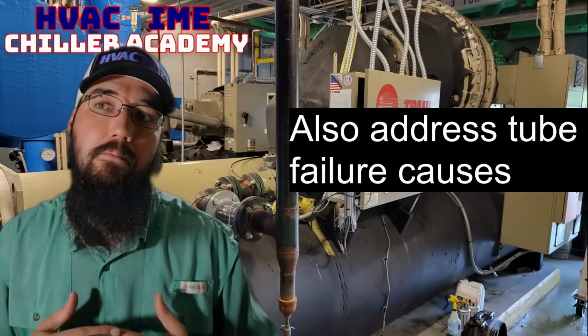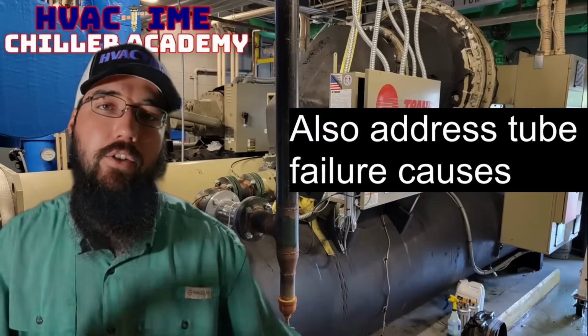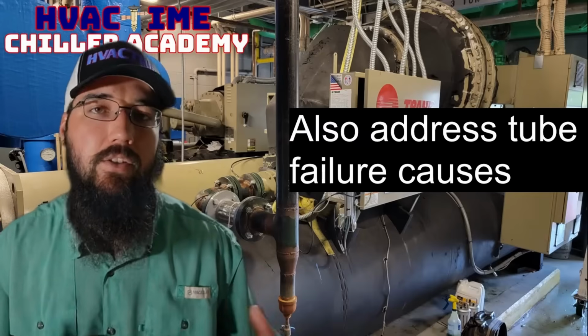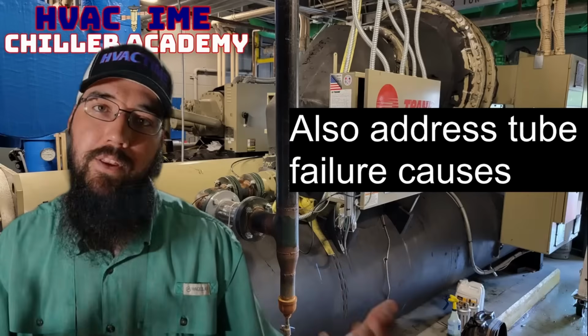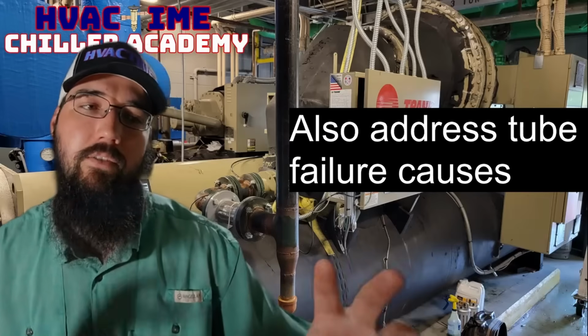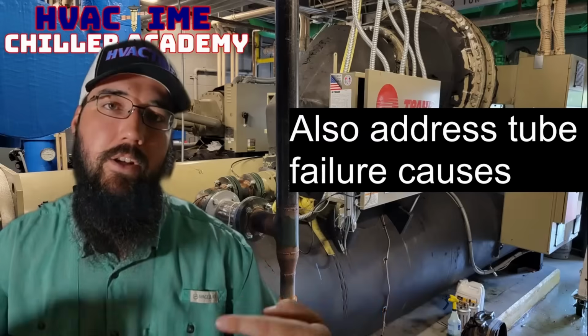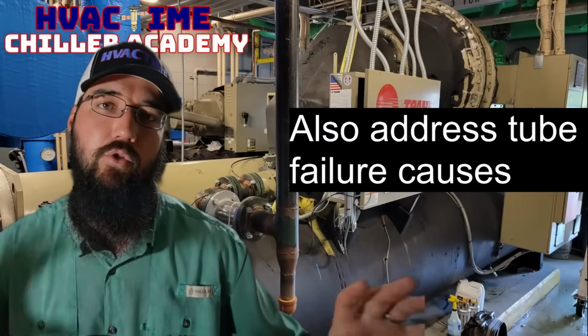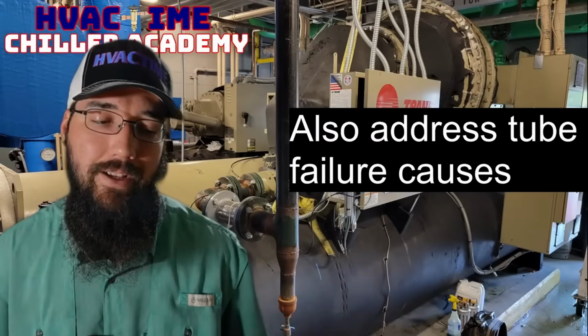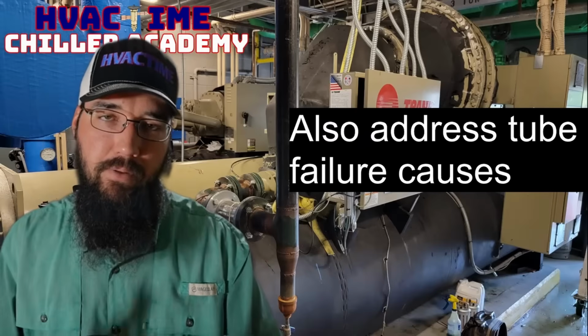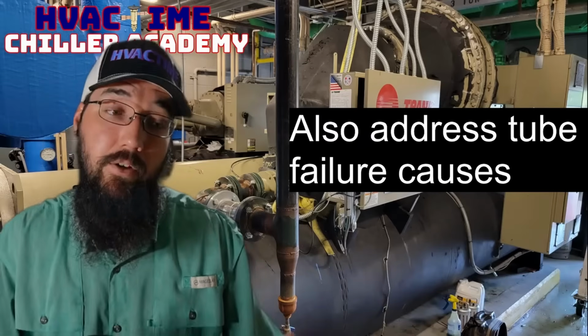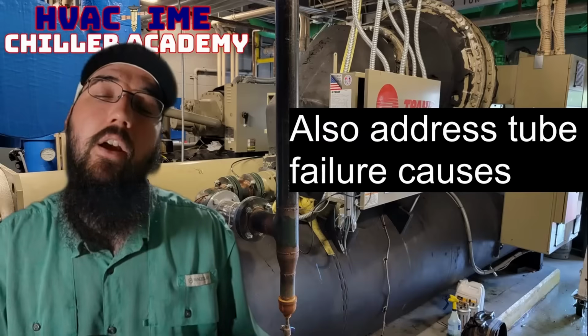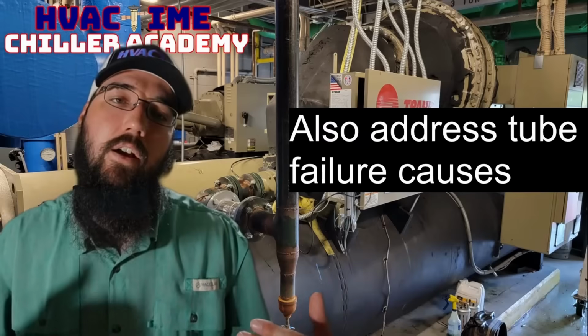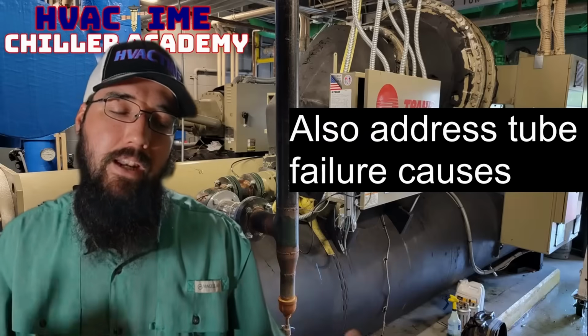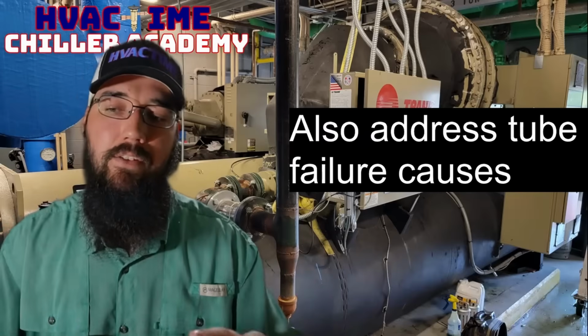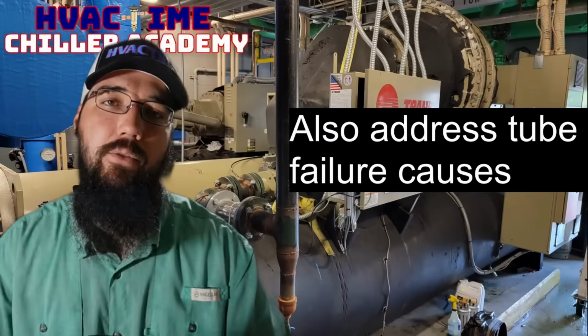That is my recommendation. You're not just going to do the ones you think are bad, because the cost of going to that extent to begin with, to bring that machine back to life, is not worth the risk of leaving old tubes in place. You end up going through and just doing all the tubes new so that everything is fresh. And that's a very extensive process. Either plugging the tube or, depending on the extent of the failure, potentially retubing the machine are going to be the primary ways of getting that leak to stop or not having it affect the rest of the machine.